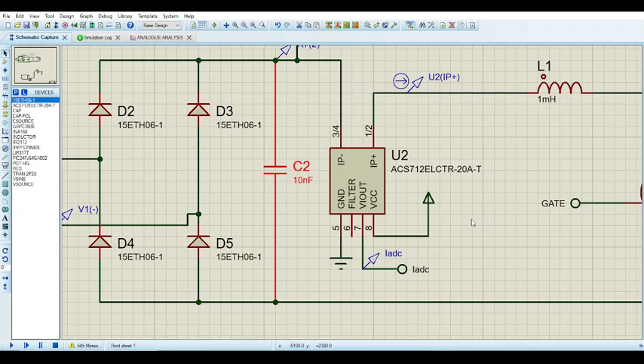I recommend you limit the sensor you use to a 15 or 10 amp sensor, because most of the time you're not even dealing with currents that high anyway. But 20 amp is safe. Cap it off at 20 amps, because 20 amps is a good balance between the current it can deal with and the accuracy. It's not too compromised, it's still fairly accurate at 20 amps. Above that, it gets kind of weird. If you're not dealing with current above 15 amps, it makes no sense to use a 30 amp current sensor, honestly.